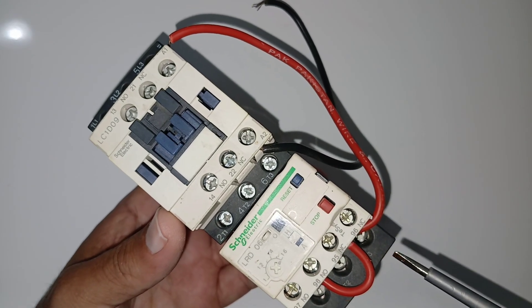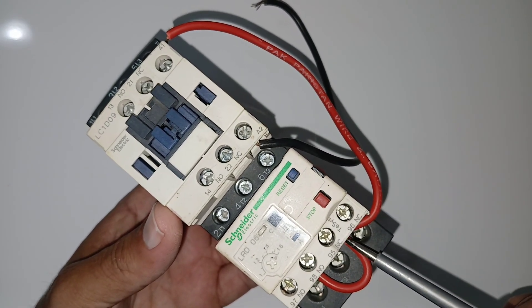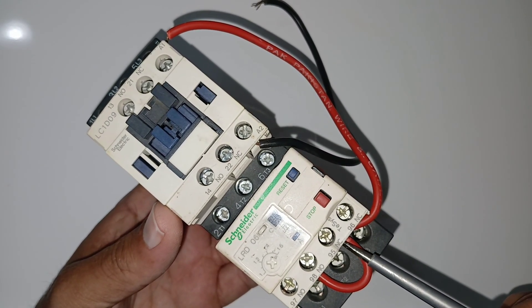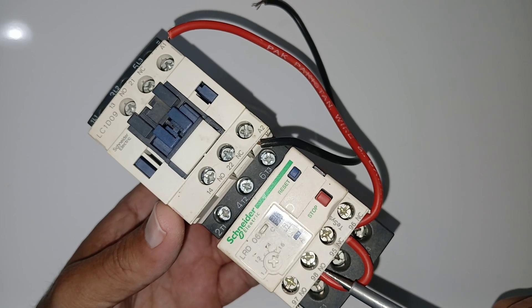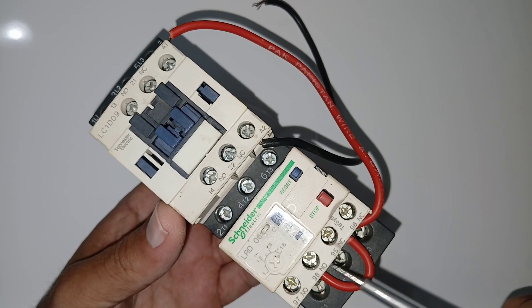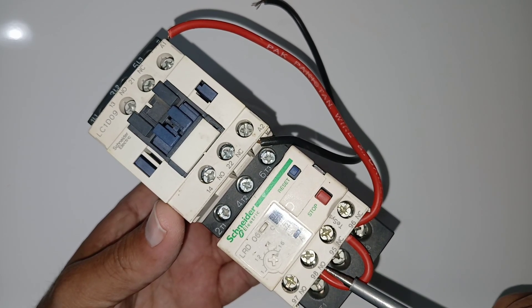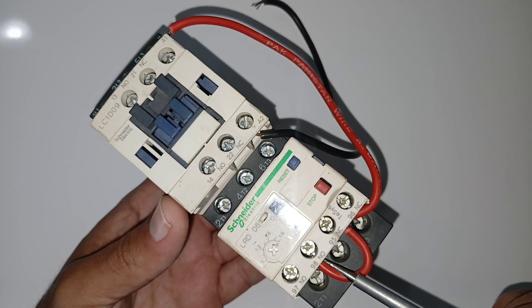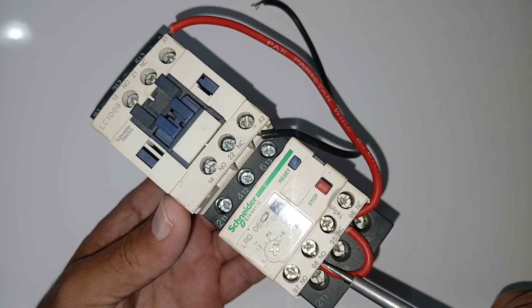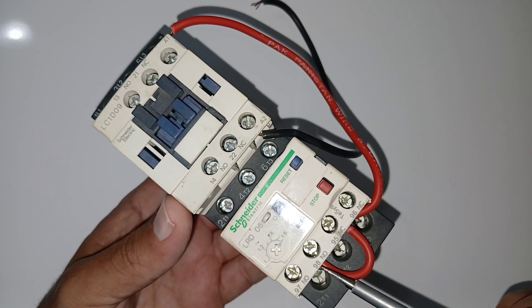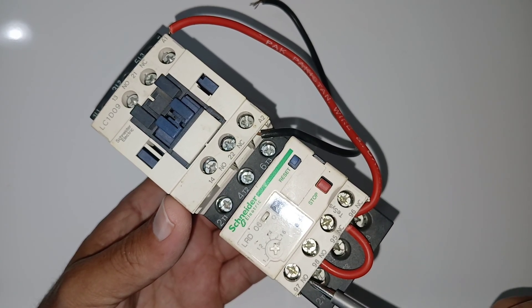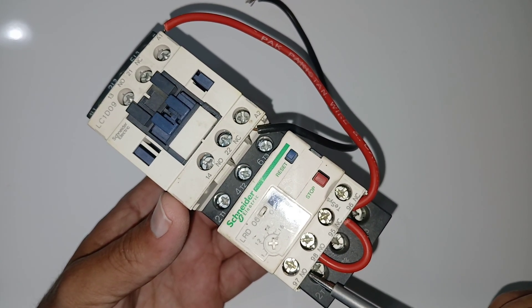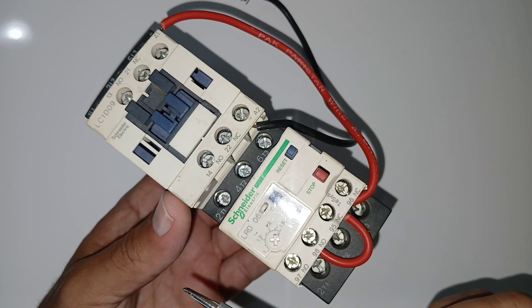And now you need to take one loop from 95 to 98, so this power will come also here. Why? Because you need to connect the trip indicator. From 97, you need to give one wire to the trip indicator.